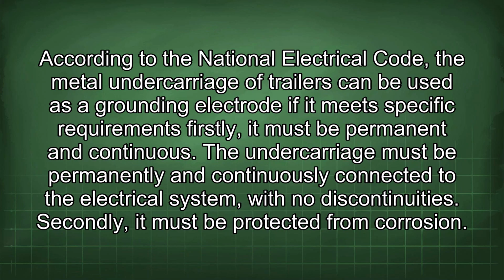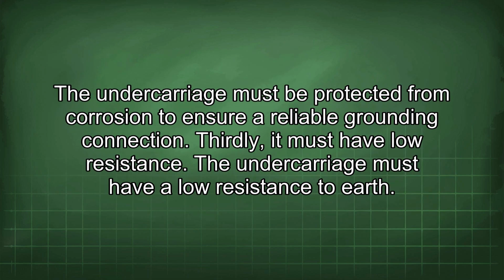According to the National Electrical Code, the metal undercarriage of trailers can be used as a grounding electrode if it meets specific requirements. Firstly, it must be permanent and continuous. The undercarriage must be permanently and continuously connected to the electrical system, with no discontinuities. Secondly, it must be protected from corrosion. The undercarriage must be protected from corrosion to ensure a reliable grounding connection. Thirdly, it must have low resistance. The undercarriage must have a low resistance to earth.